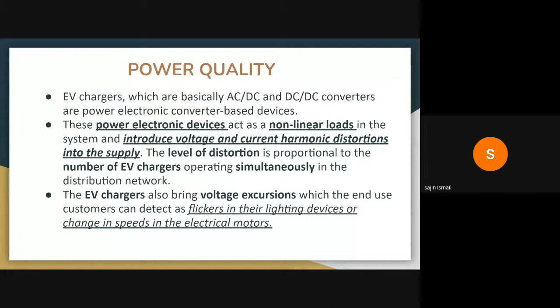So the EV chargers also bring voltage excursions, which the end use customers can detect as flickers in the lighting devices or change in speed in the electrical motors. Another problem it can create, as I said earlier, is voltage imbalance due to the harmonics. The waveform will be totally distorted. So these distortions and imbalances can create voltage excursions. It will vary from one point to another, and can even create flickers in the fluorescent lights and incandescent lamps. At the same time, the speed of electrical motors like your fans and other equipment will also vary because the voltage is changing.